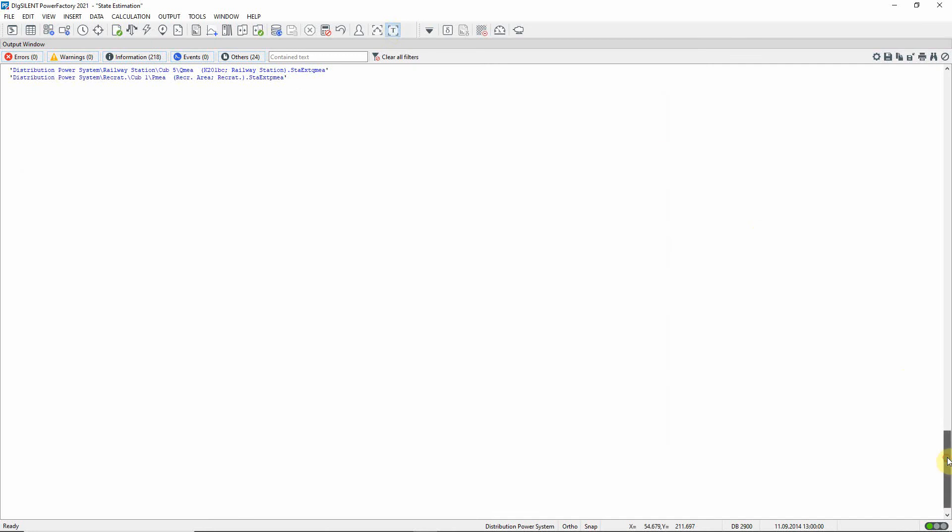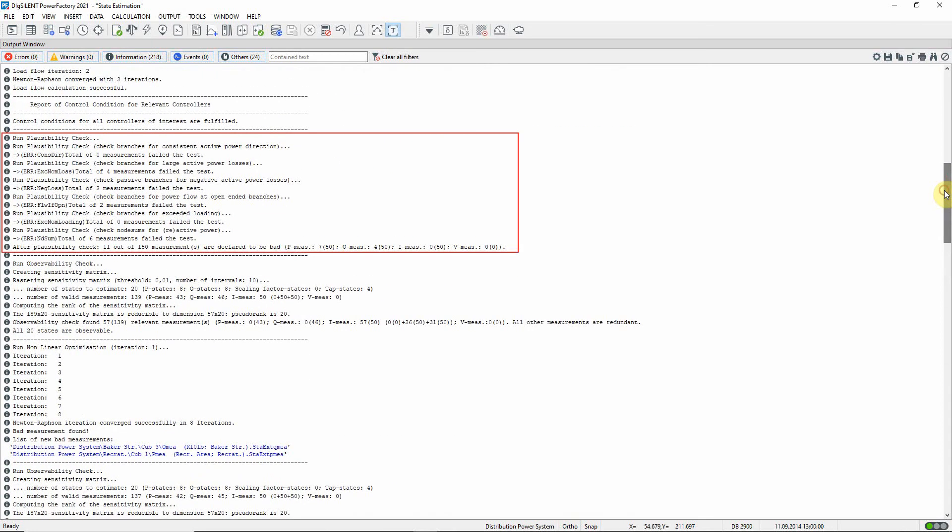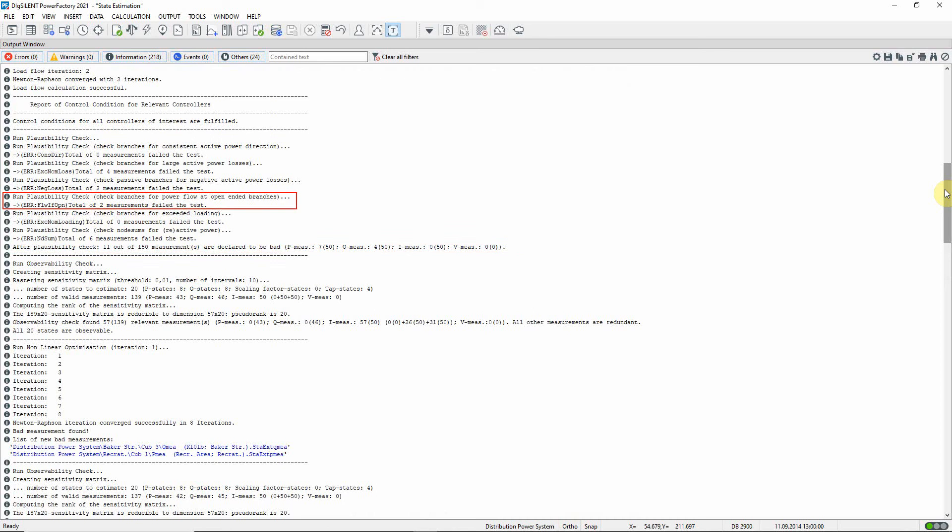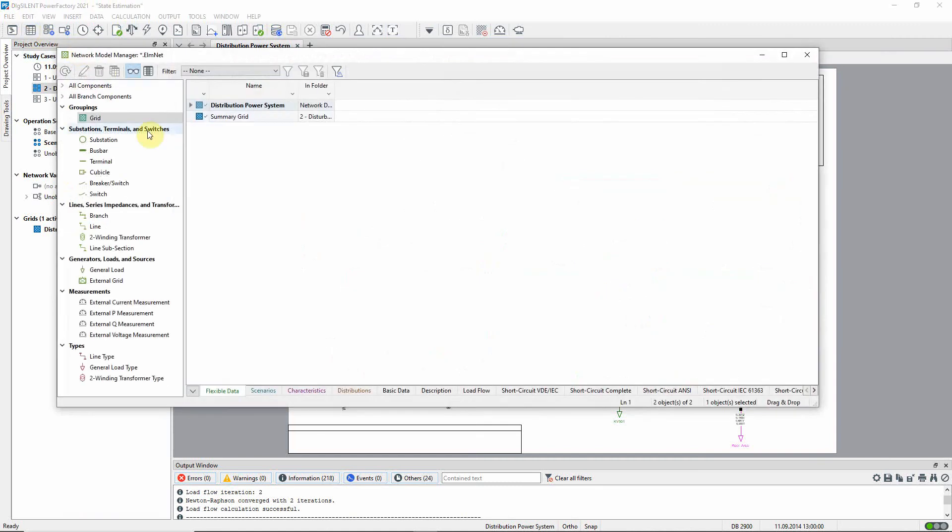Looking in the output window, we can see that the plausibility check has detected some implausible measurements. Measurements that are to be ignored. For example, two measurement devices failed the test of having non-zero flow on an offloaded circuit. Details can be seen in a network model manager.